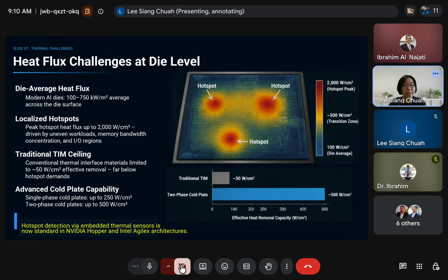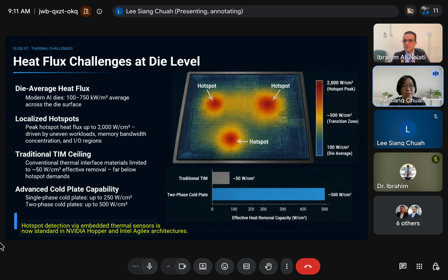At the die level, the challenge is highly non-uniform. A modern AI chip will see average heat flux of 100 to 700, but local hotspots can reach about 2000, driven by uneven compute, memory, and input-output activity. The problem is that conventional thermal interface material can only handle about 50 units. Regarding cooling approach, single-phase cold plates reach about 250, while two-phase systems can reach up to 500, with significant engineering complexity.